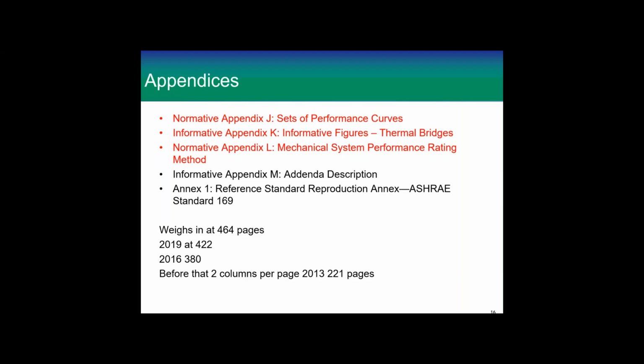So this means that everybody will be using the same curves, and so all the designers will have an even playing field. Plus, these curves should be beneficial because they are actual curves for good chillers. Now, if you don't have one for the building you're proposing to build, then you can use them there too. But they're designed for your baseline building so that everybody has the same curve they're working from. It's fairly standardized. Informative Appendix K are some figures.